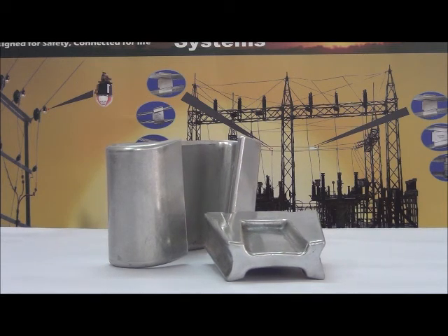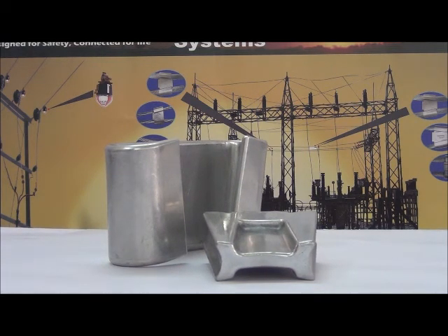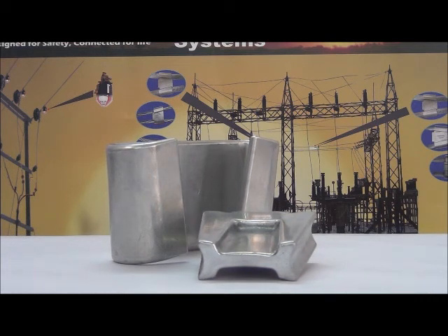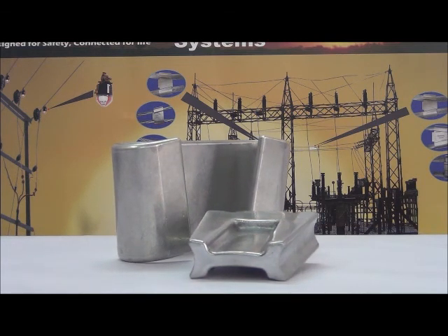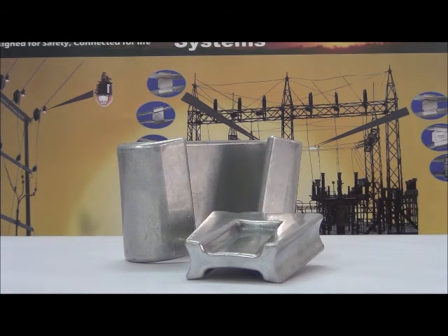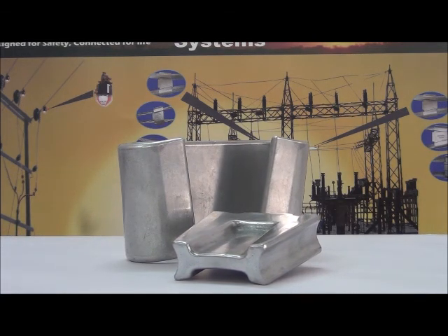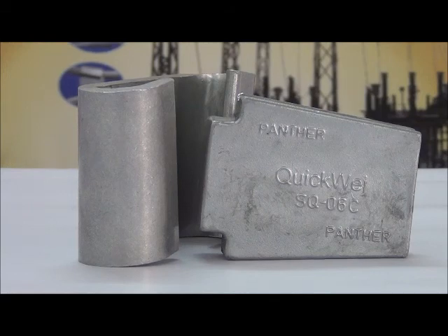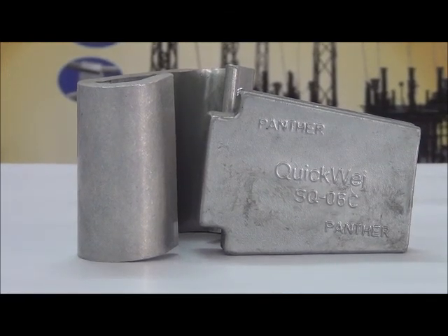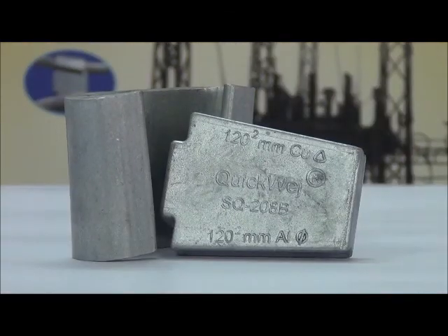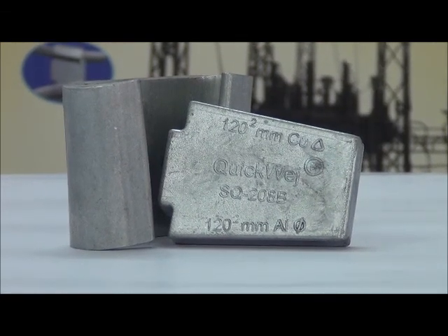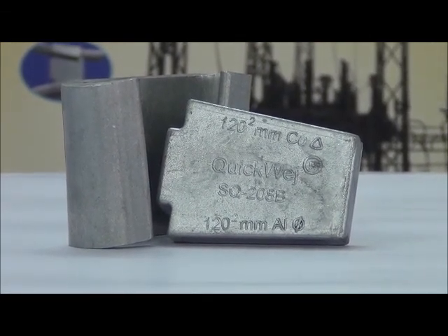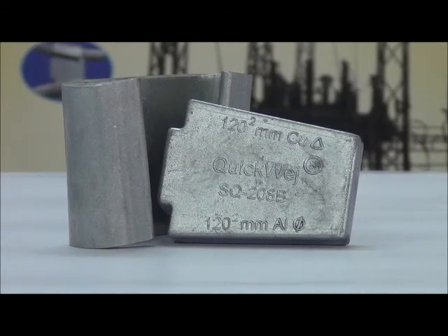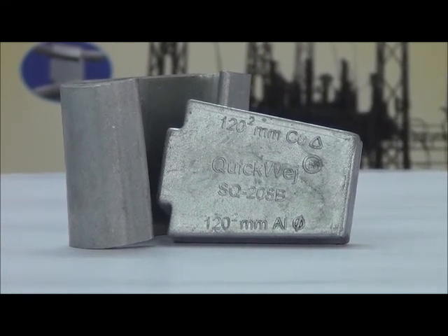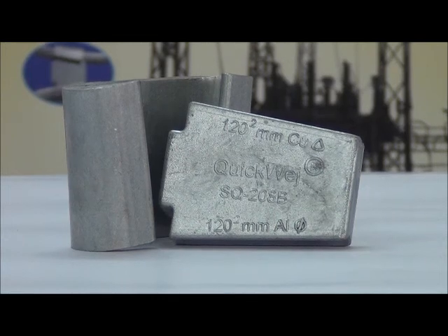Though the concept of wedge connectors has been adapted in the industry for quite some time, users have always faced practical issues in handling the existing ones. Sun Electric's QuickWej is a clear solution for this. QuickWej incorporates a rigid wedge and a C-shaped spring member. During installation, the wedge is mechanically driven into the C member, spreading the C member, which in turn places high forces on the conductors for a reliable and stable connection. The wedge is driven by way of a simple hammer.